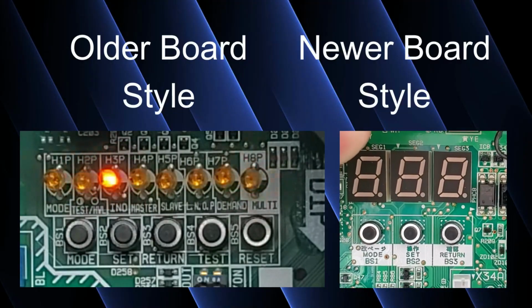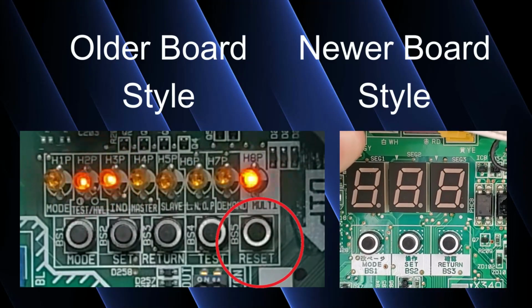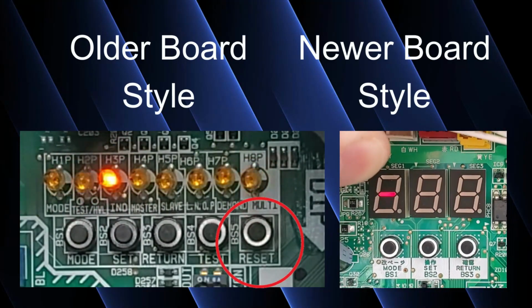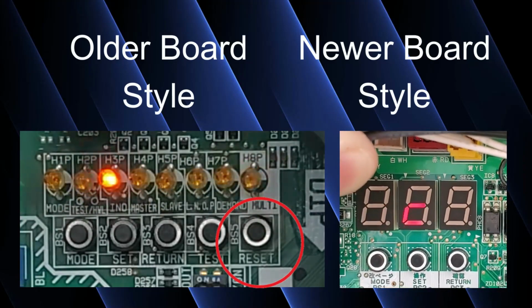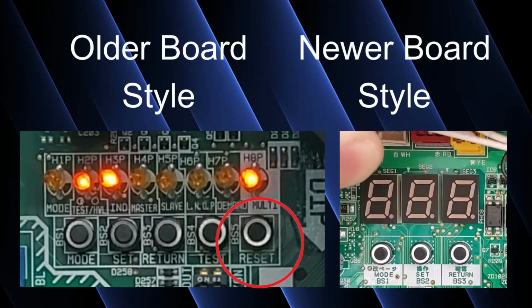If you did that, good job for starters, you listened. Now you need to power up the outdoor unit, the condenser, because you have powered everything else already. This time when you power up the outdoor unit, you need to press and hold the reset button on the older style board, the board that has all the LEDs on it.